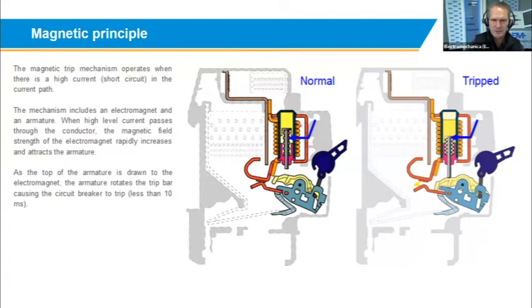the breaker. You've got this coil going around a tube, and this coil will create a magnetic field. When there's a massive short circuit going through the product, this will create a force and push down the plunger and hit the trip bar, and again it will open the product very quickly. They say in less than 10 milliseconds, which is fast, because the longer you keep that short circuit on your installation, the more damage it can cause to your installation, your cables and everything else. So you need to open the short circuit as quickly as possible. That's the explanation for the thermal part and the magnetic part. Going forward, if they talk about thermal magnetic, you understand thermal is overcurrent and magnetic is the short circuit principles.